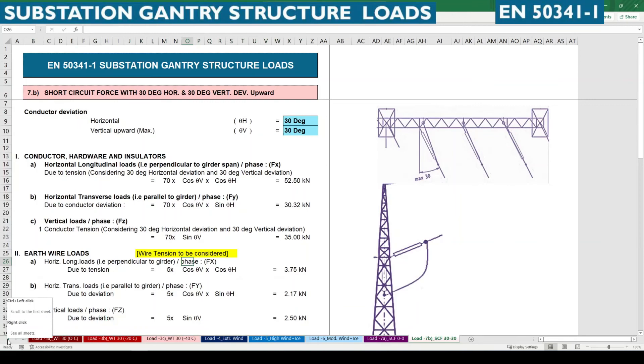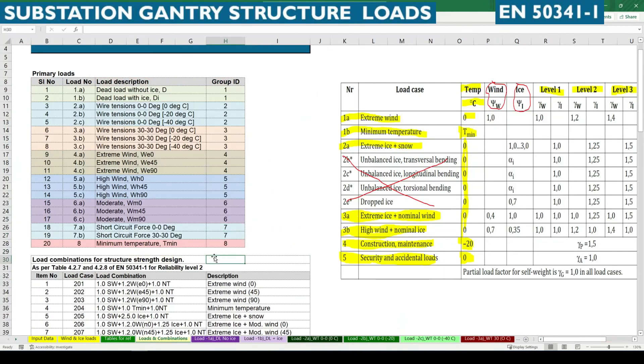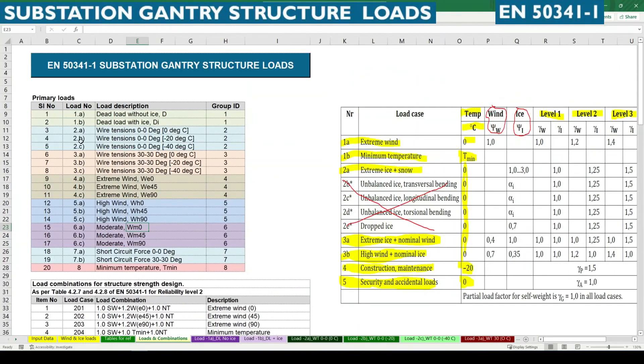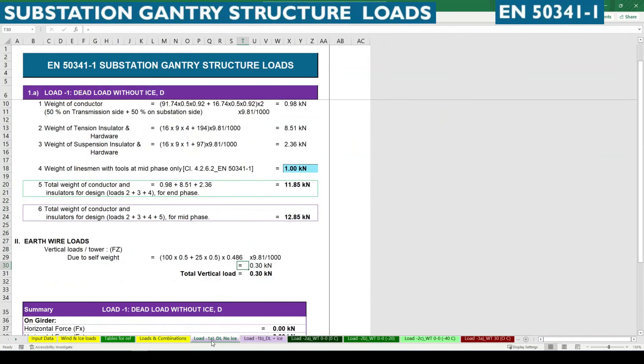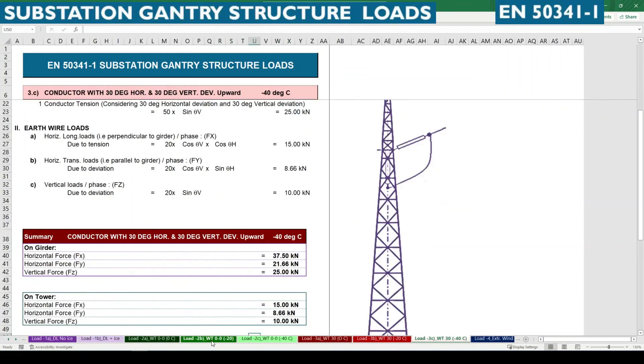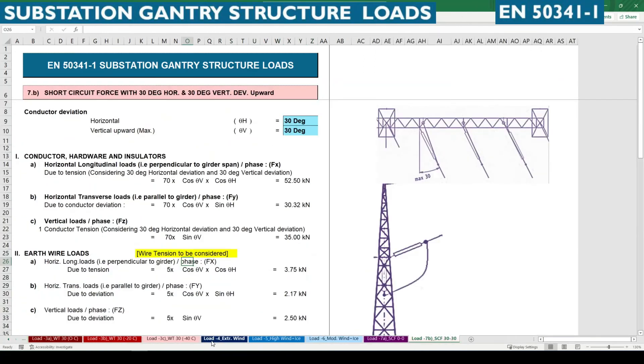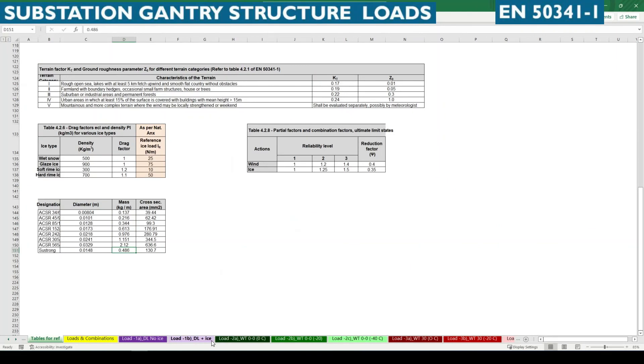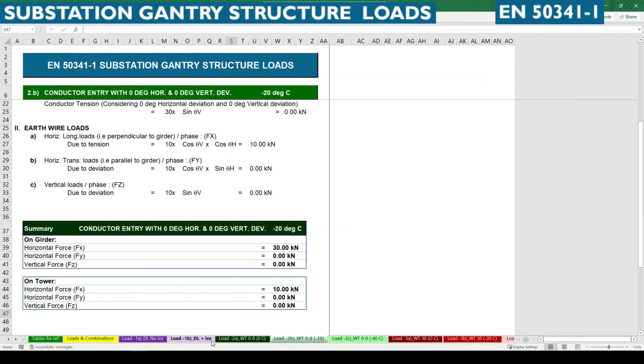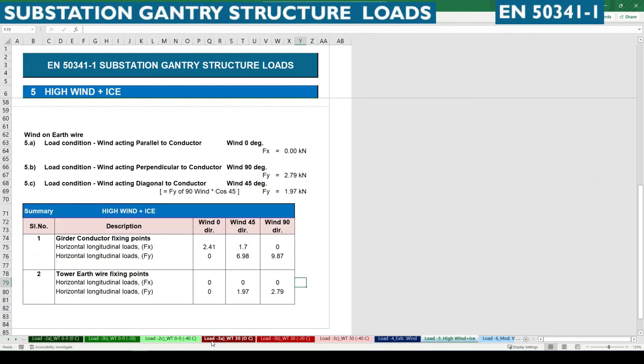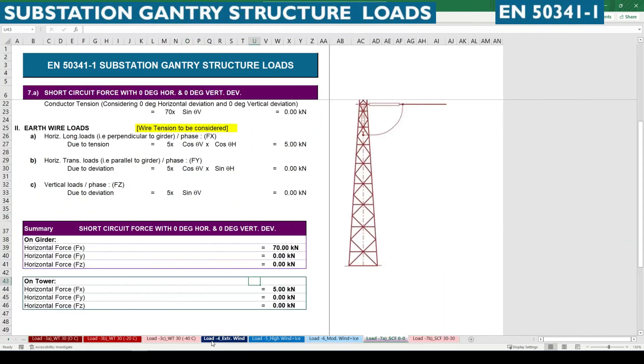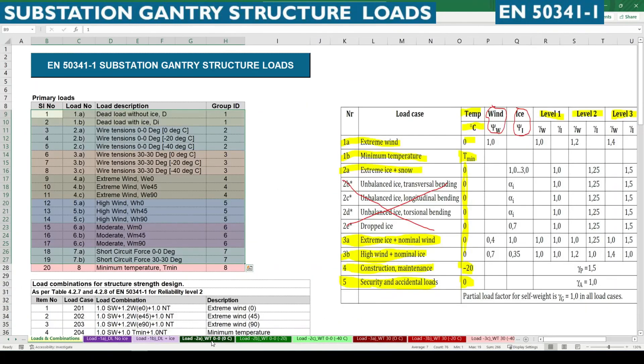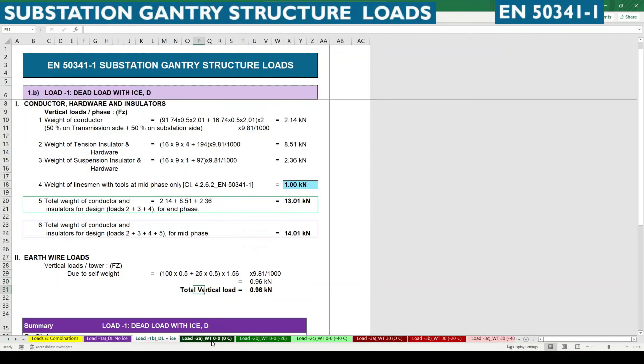These cover all the short circuit force direction and magnitude calculations. Finally, we have calculated all 19 numbers of primary loads. Once this is done, we need to input all the load values into the structural model we had already prepared. Links for creating the model in both STAAD.Pro and Robot Structural Analysis are given in the description. From the next video onwards we are going to apply these loads into the model and do all the design calculations, analyzing the model and designing members and connections based on European standards.